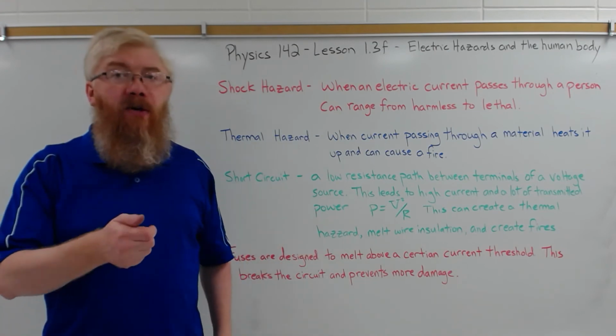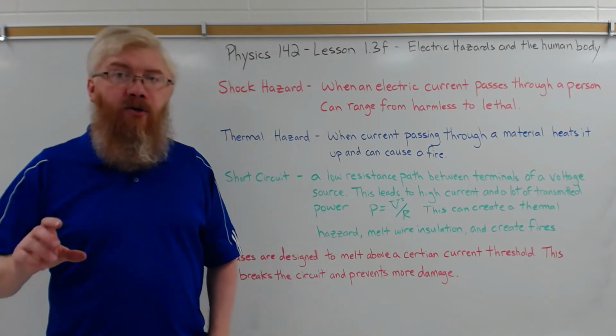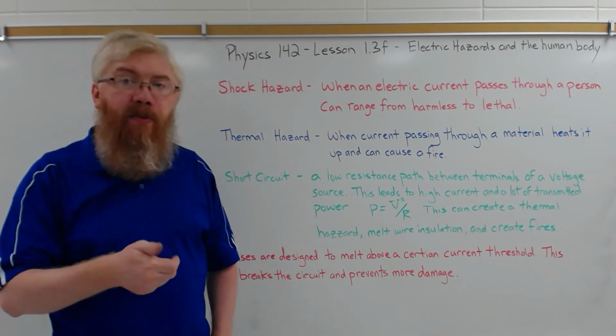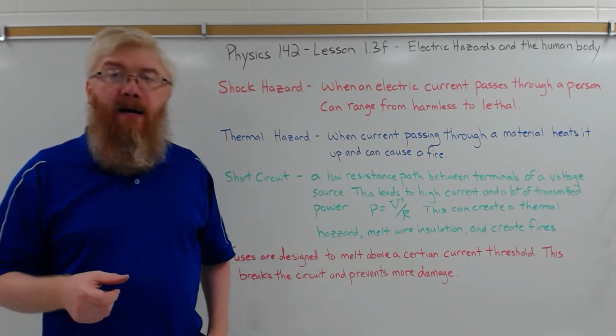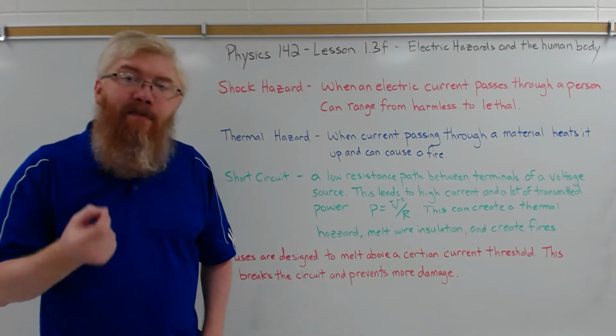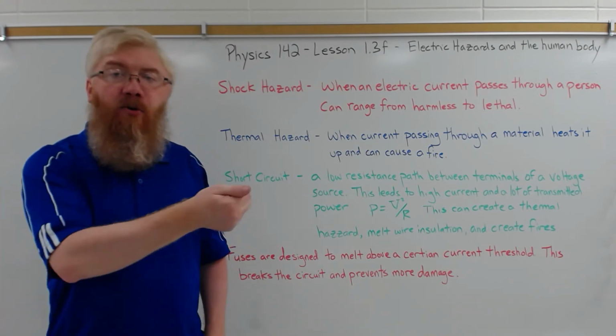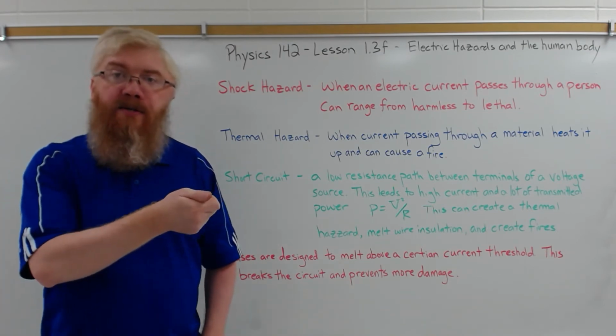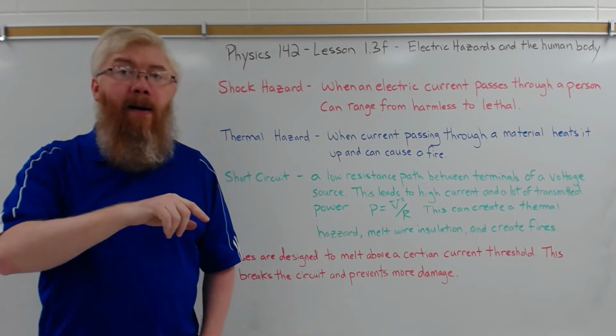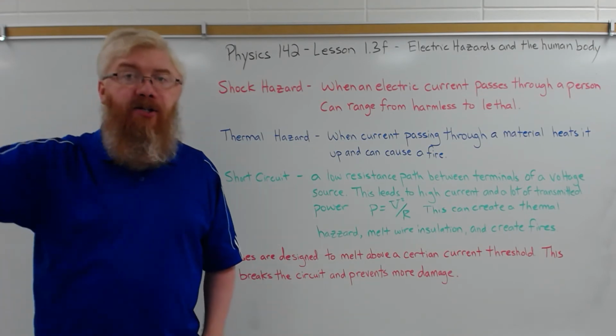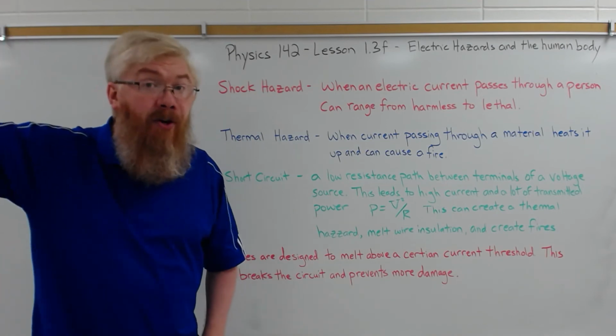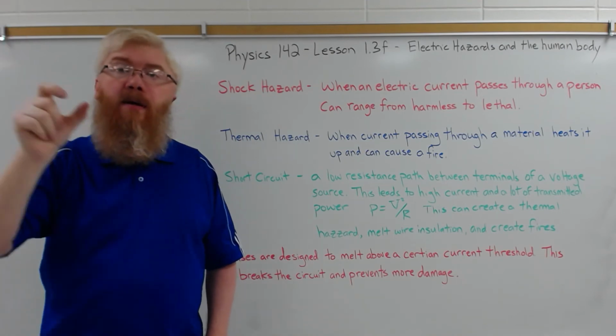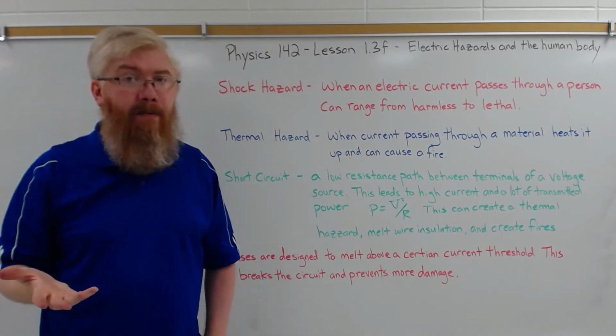Do not use a fuse that's not rated properly. Don't put a 30 amp fuse when you should be using a 15 amp, because fuses are designed to melt before the wires in your house. If you put too big a fuse in, an improper fuse, that fuse will keep the current going past the safety recommendations for the wiring in your house, and the insulation will melt before the fuse does, and that's bad. That's an electrical fire.